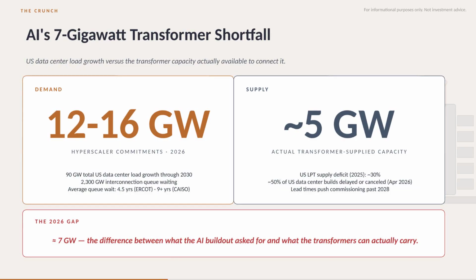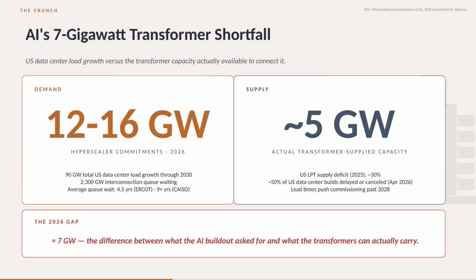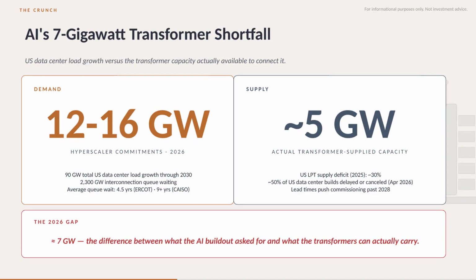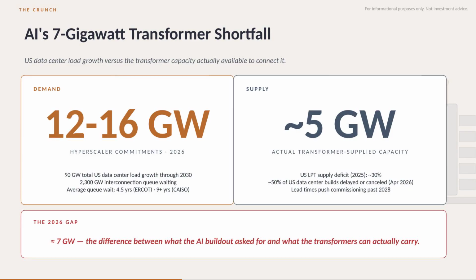For 2026 specifically, hyperscalers have committed 12 to 16 gigawatts of new data center capacity. The actual transformer-supplied capacity available is closer to 5 gigawatts — a 7 gigawatt shortfall — and the consequence is already visible. As of April 2026, roughly half of U.S. data center builds are delayed or cancelled.